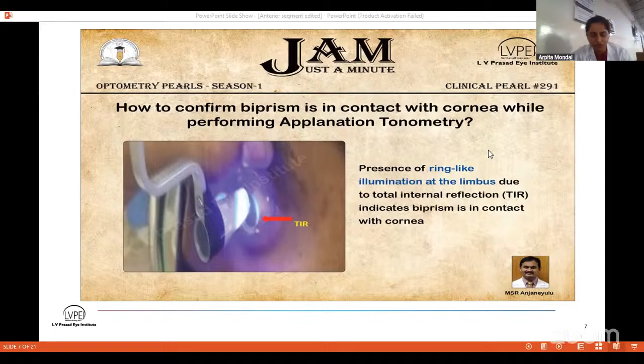When you bring the biprism close to the cornea with the cobalt blue light on, you get two media. The first one is the prism, which has a higher refractive index, and the second one is the tear film or cornea, which has a lower refractive index. The cobalt blue light shines into the biprism. Light inside the biprism hits the prism and tear interface, so light gets reflected back. It is completely bounced back, and the reflected light appears as a bright ring. Only then can you know that the prism is in perfect touch with the cornea.